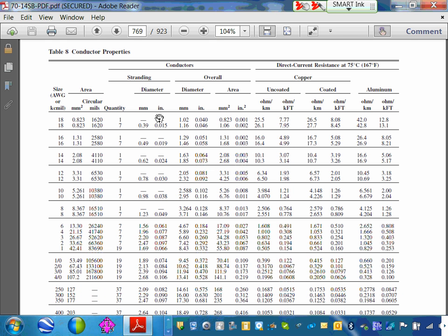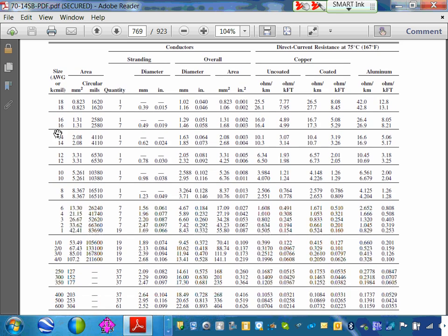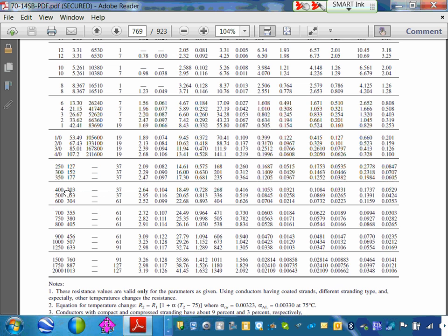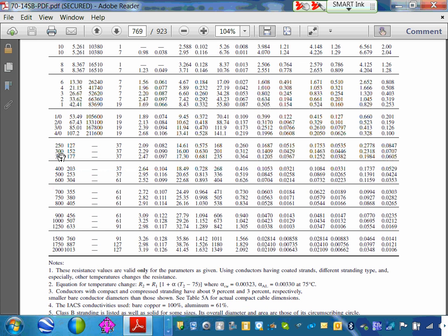Okay. Now, what did we come up with? 300. So can you guys go under wire size right here? KCM, wire size, AWG or KCM. So you can go from 18 all the way down. Do you see 300 here? Is it a wire size then? Yes. Now, what happens if I came up with 305? What would you do? Next size. You don't go down. Down is dangerous because it's less safe. You go up. So if you came up with 301, it becomes 350.